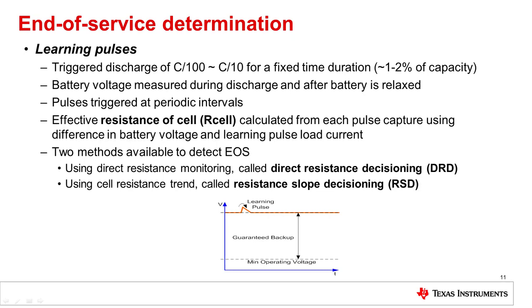The learning pulses use a discharge level on the order of C/100 to C/10 for a short time duration, discharging a limited amount of capacity — typically one to two percent. The device monitors the voltage, current, and temperature of the cell during the entire relaxation period, during the discharge, and during the post-relaxation. These pulses are triggered periodically — once a month or once every few weeks. From each learning pulse, we calculate a resistance of the cell, called an R cell. We store that value into the device and then analyze the R cell values and their trend over time to determine whether the cell is approaching the end of its usable life.